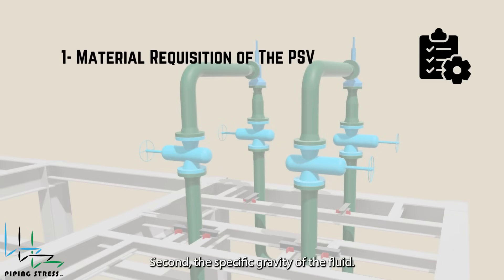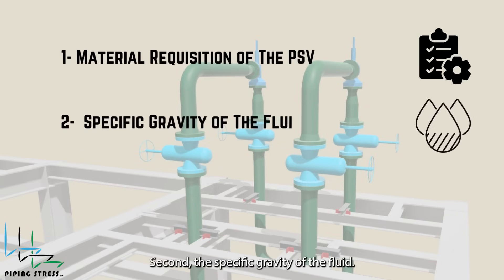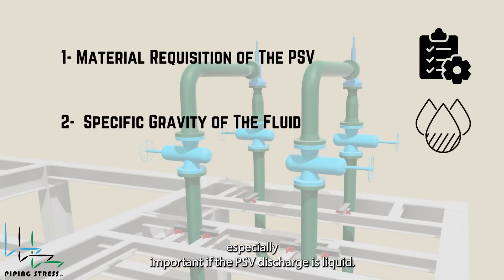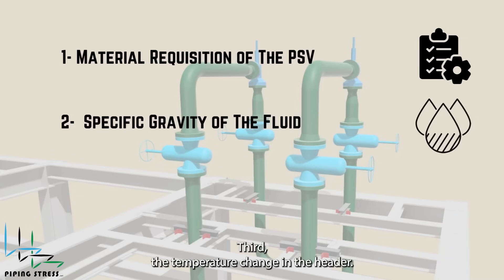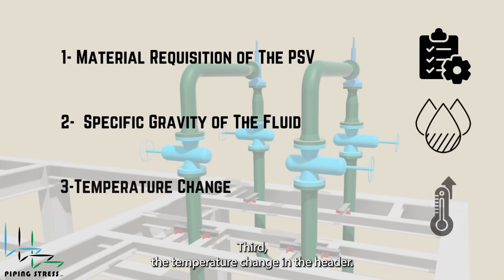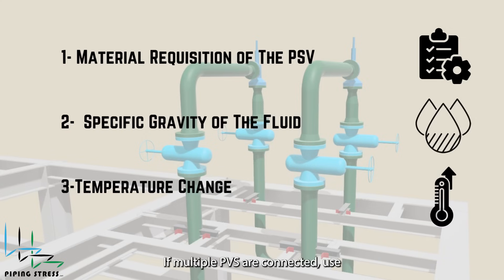Second, the specific gravity of the fluid — this is especially important if the PSV discharge is liquid. We also need the specific gravity of the connected header. Third, the temperature change in the header. If multiple PSVs are connected, use the average temperature for calculations.